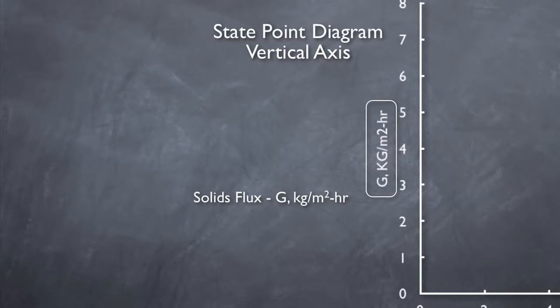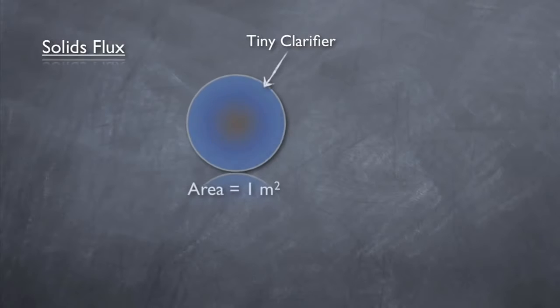In this case, the solids flux is the mass of solids passing through the clarifier in one hour normalized to one square meter of clarifier area. Now that was a mouthful, let's try and simplify it. Imagine a tiny clarifier with a surface area of only one square meter.